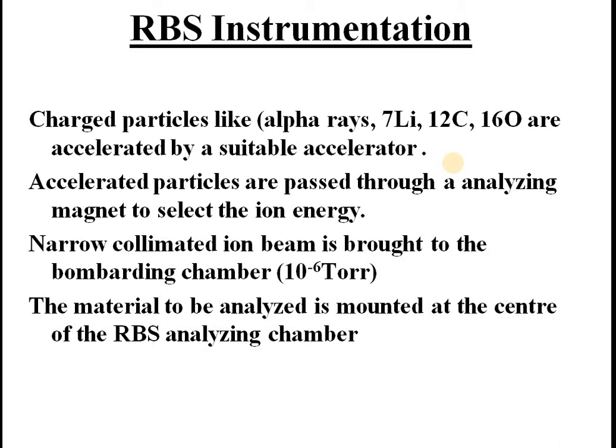The material to be analyzed is usually mounted and fixed at the center of the RBS chamber. That fixing system is called a target holder. Usually a ladder system is used. In a ladder system, you can fix a number of targets together, and each one can be successively irradiated with the beam.